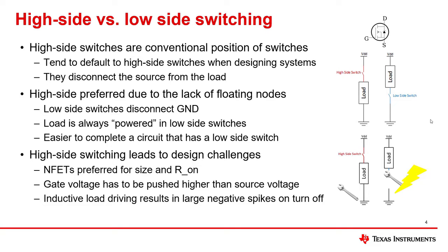Often, high-side switching is preferred because in a low-side switching system, the load is always active or powered. Therefore, in the event of a dropped wrench or frayed wires, it is easier to mistakenly complete a circuit that is using low-side switches. Please note that this does not mean that there is no place for low-side switching in the industry. This is because there are major challenges when using high-side switches.